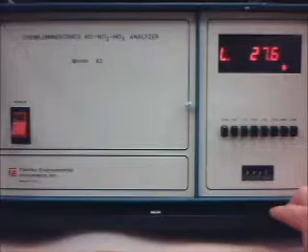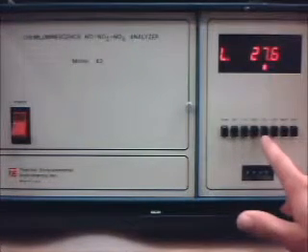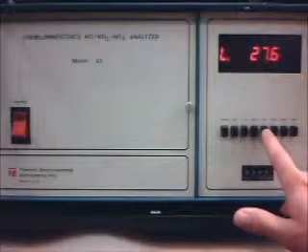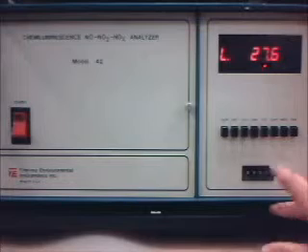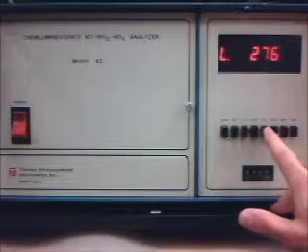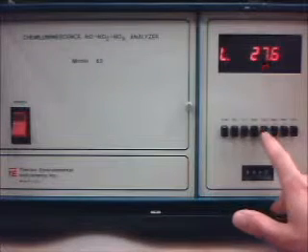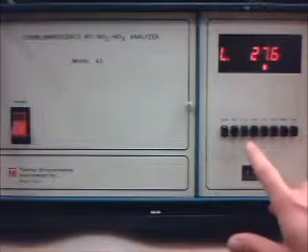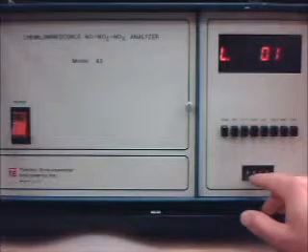Anyway, the next button is this calibrate button, CAL. We push it, and it should allow for a calibration of first NO. When you push it again, NO2, and then the third actuation is NOx. But let's try. If I hit enter, if I hit calibrate. See, I haven't quite figured this out yet, as you can tell.